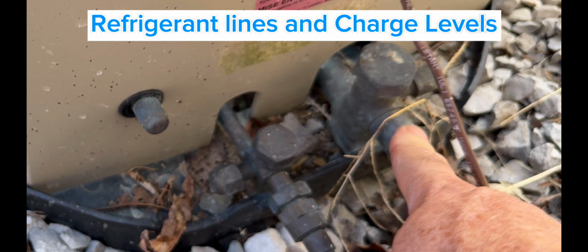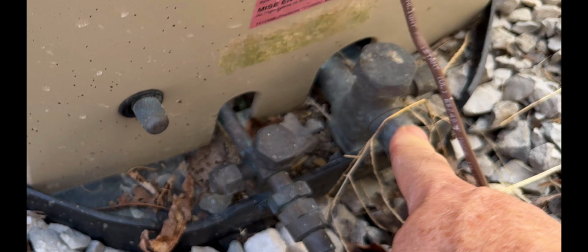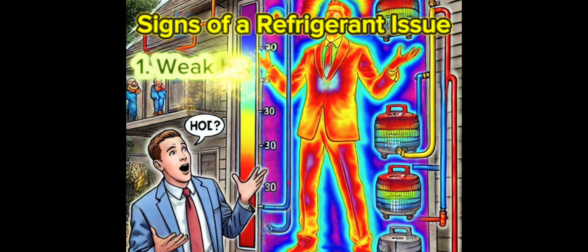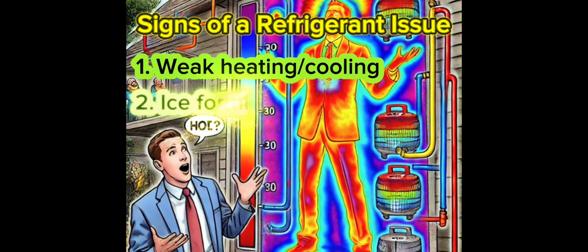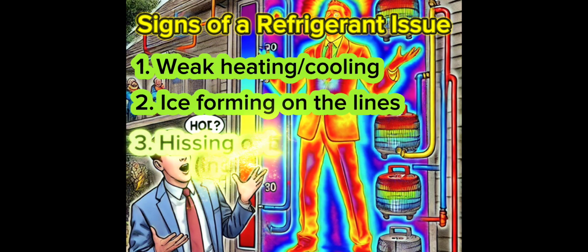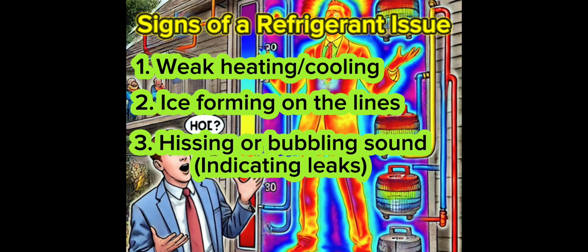Refrigerant is the lifeblood of your heat pump, transferring heat between the indoor and outdoor coils. If your system's low in refrigerant, it won't heat or cool properly, and running it that way can damage your compressor. Refrigerant leaks or incorrect charge levels lead to weak performance, icing on the coils, and skyrocketing energy bills.